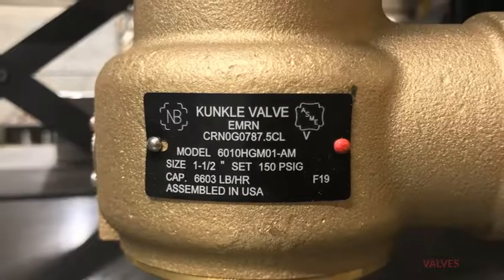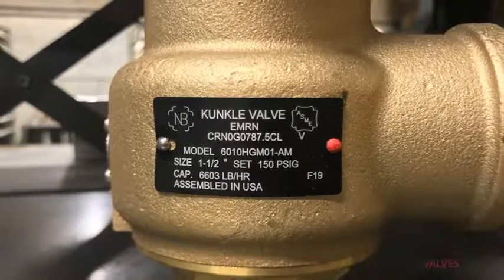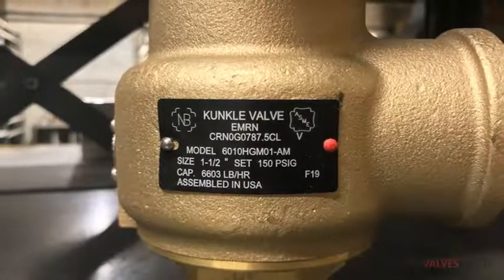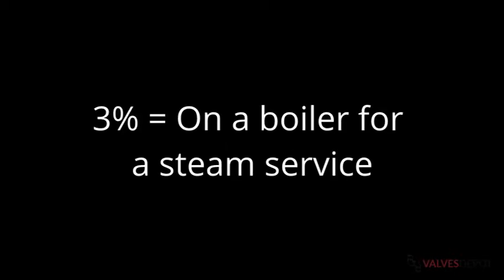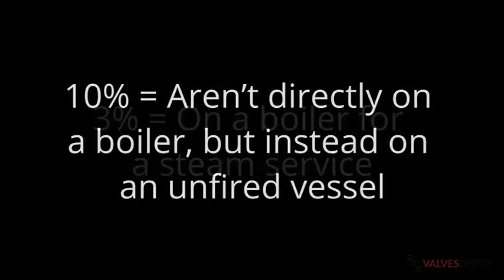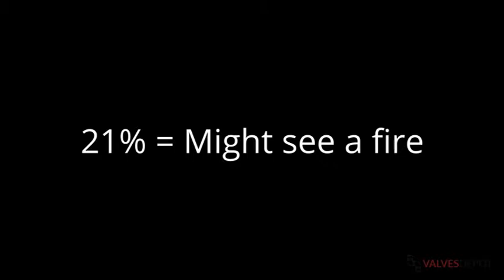Your allowable overpressure helps determine the valve's code stamp and generally depends on where you're using the valve. There are three options for allowable overpressure: 3%, 10%, and 21%. 3% is for valves that are on a boiler for a steam service. 10% is for valves that aren't directly on a boiler but instead on an unfired vessel. And finally, 21% is for valves that might see a fire.